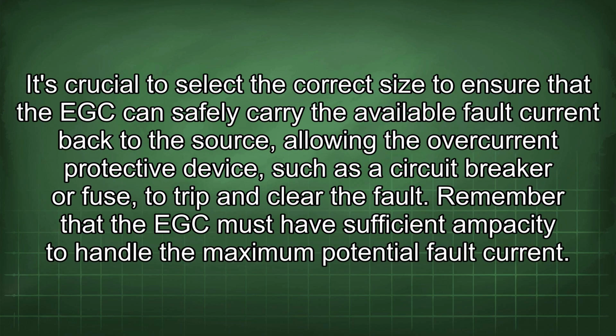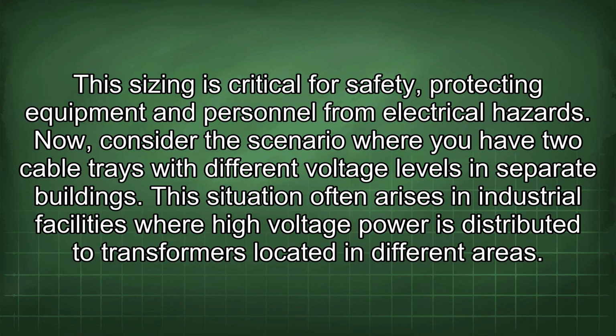It's crucial to select the correct size to ensure that the EGC can safely carry the available fault current back to the source, allowing the overcurrent protective device, such as a circuit breaker or fuse, to trip and clear the fault. Remember that the EGC must have sufficient ampacity to handle the maximum potential fault current. This sizing is critical for safety, protecting equipment and personnel from electrical hazards.